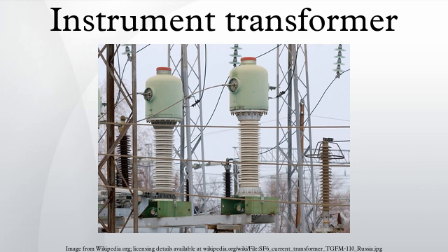Care must be taken that the secondary winding of a CT is not disconnected from its low impedance load while current flows in the primary, as this may produce a dangerously high voltage across the open secondary and could permanently affect the accuracy of the transformer. Multi-ratio CT. The secondary winding can be single ratio or have several tap points to provide a range of ratios.